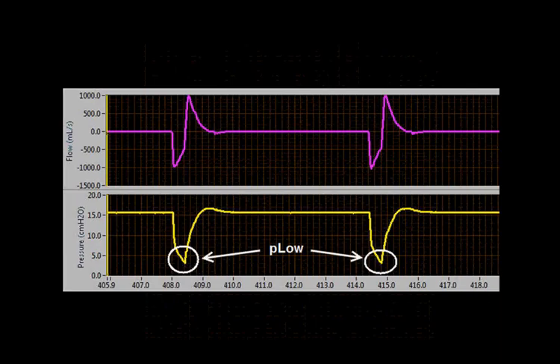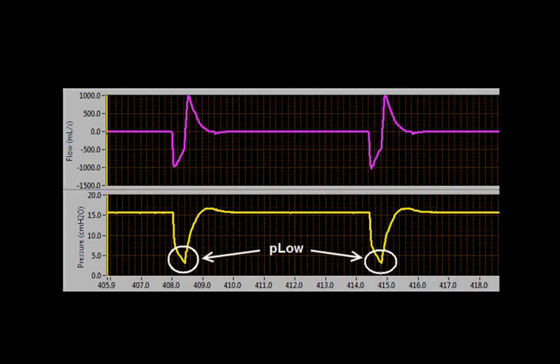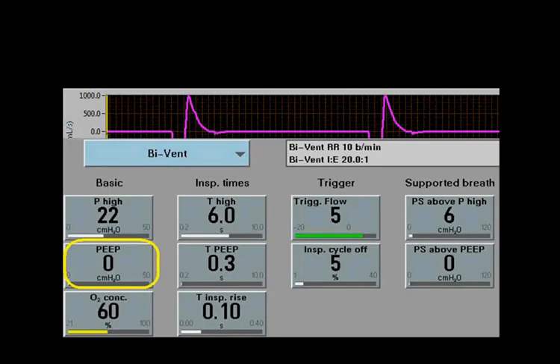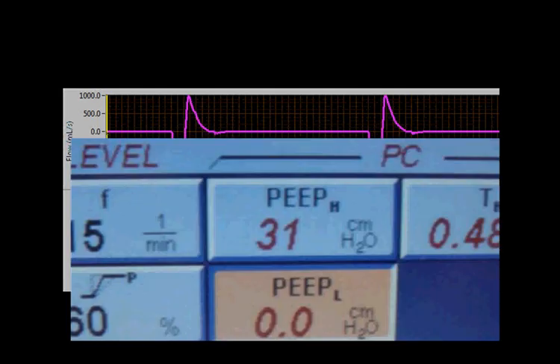The P-Low setting sets the lower level of CPAP pressure during the release phase. In the Vela and Hamilton ventilators, it is termed P-Low. In the Servo-I, it is just the PEEP setting — P-Low is the PEEP. And in bi-level on the 840, it is simply referred to as P-Low or low PEEP.